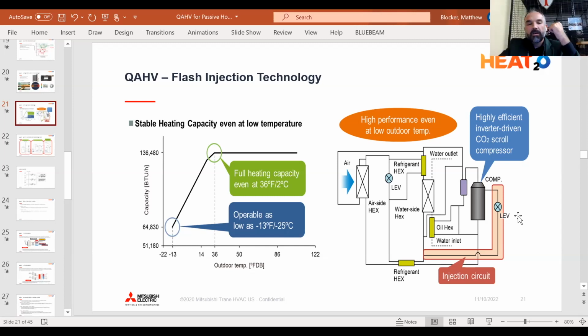Matt, can you verify that this operates kind of similar to the defrost cycle on our standard systems, where it never actually goes into full defrost mode? It defrosts section by section, so you don't actually lose heating production capacity while it's in defrost. For this system, it isn't that simultaneous defrost like we have available on the VRF that can do circuit by circuit. It would stop your production of heating for that small window of time, and stop your water circulation pump and everything going to the tanks, defrost quickly, and then get back into operation. And all that defrost derate is already built into the program, so it's going to tell you what your defrost derate is and account for that in your overall BTU calculation.